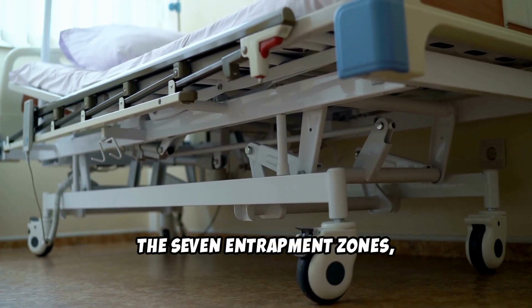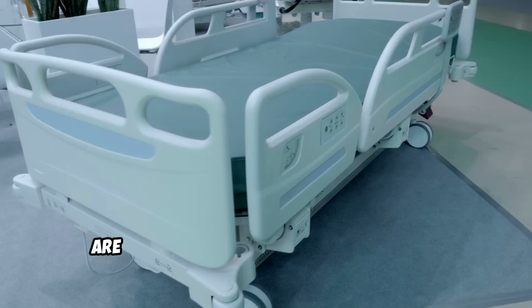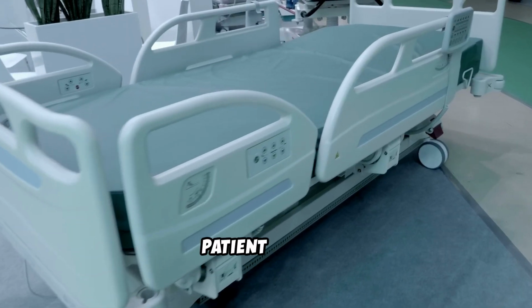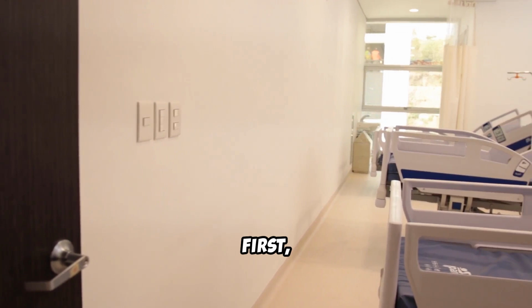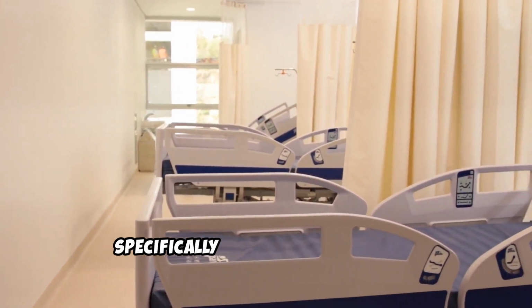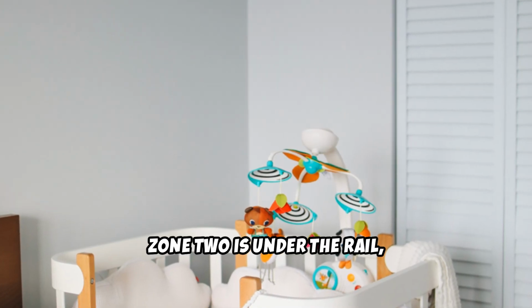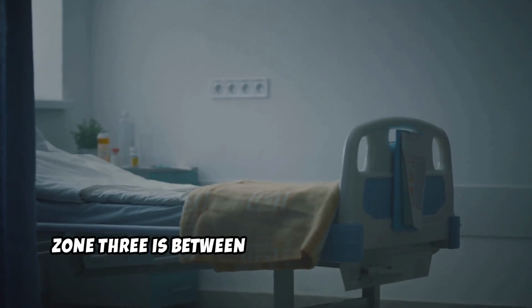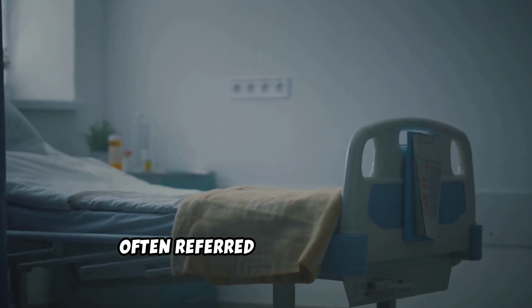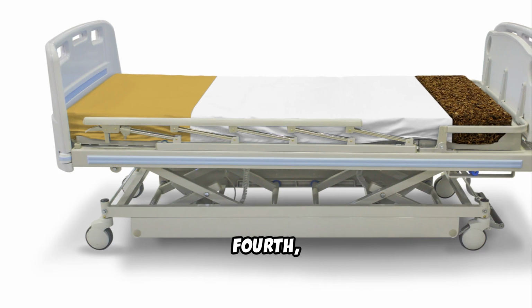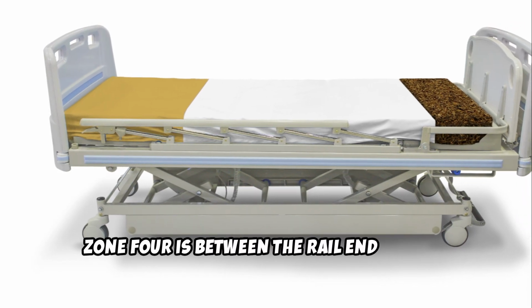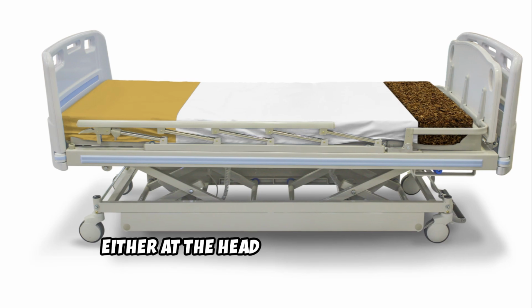The 7 entrapment zones, as defined by the FDA, are crucial to understand for ensuring patient safety. First, Zone 1 is within the rail, specifically between the rail bars. Second, Zone 2 is under the rail, found between the rail bottom and the mattress. Third, Zone 3 is between the rail and the mattress, often referred to as the side gap.